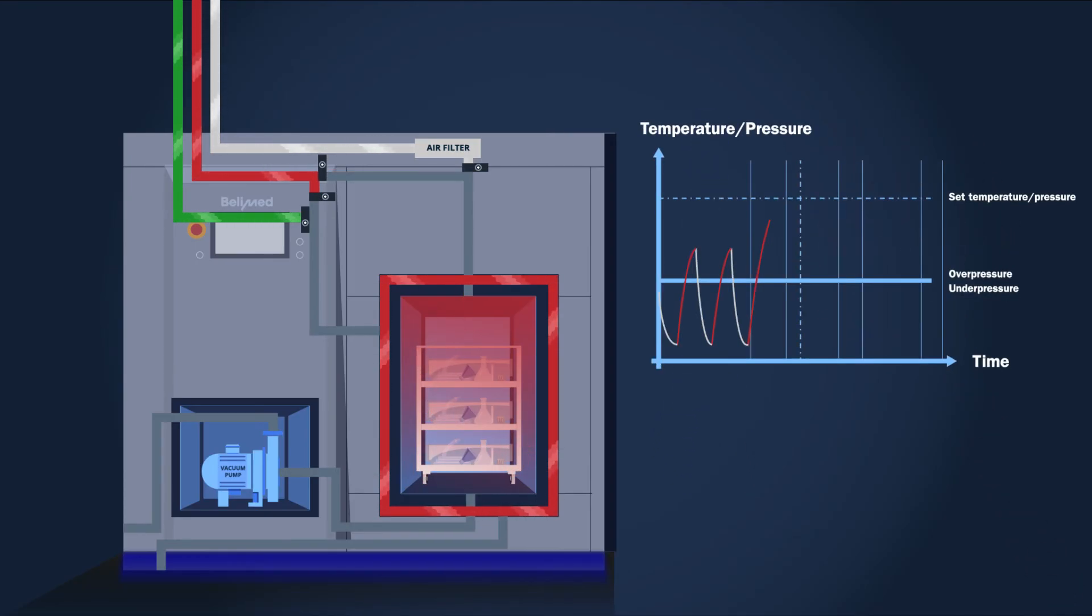After that, it is time to dry the sterilized goods. The vacuum pump evacuates the steam from inside of the chamber and the steam in the chamber walls is released.